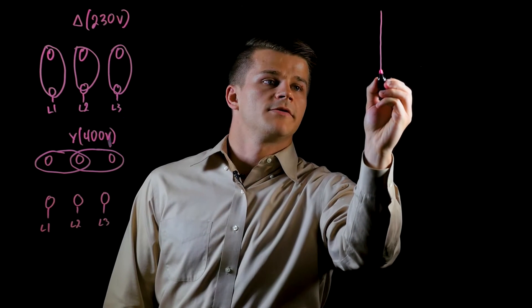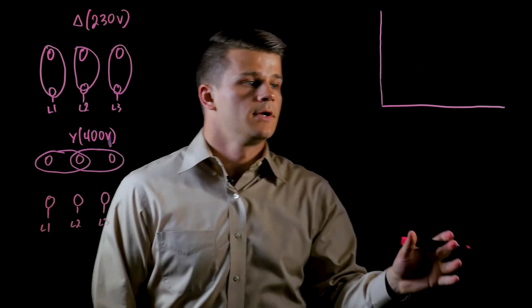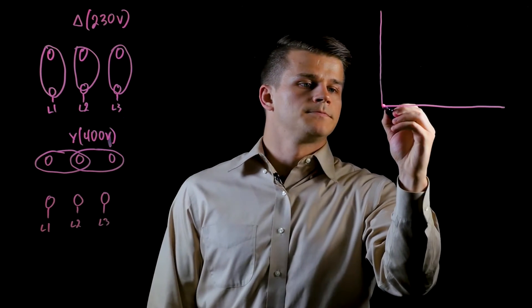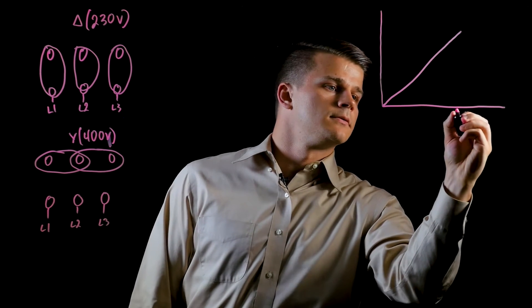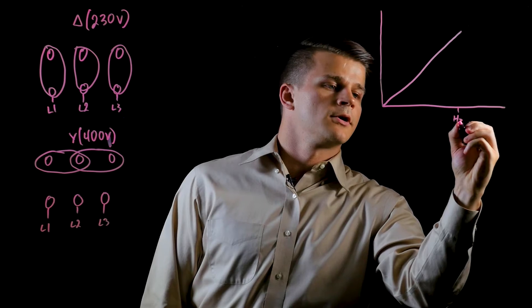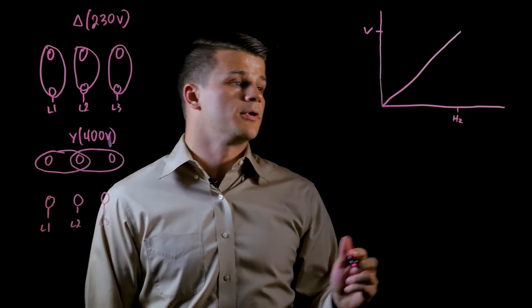Now that we've talked about voltage and frequency, we'll see what effect that actually has. In standard open loop motor control, as long as you maintain a constant ratio between voltage and frequency, you will have constant torque on your output.